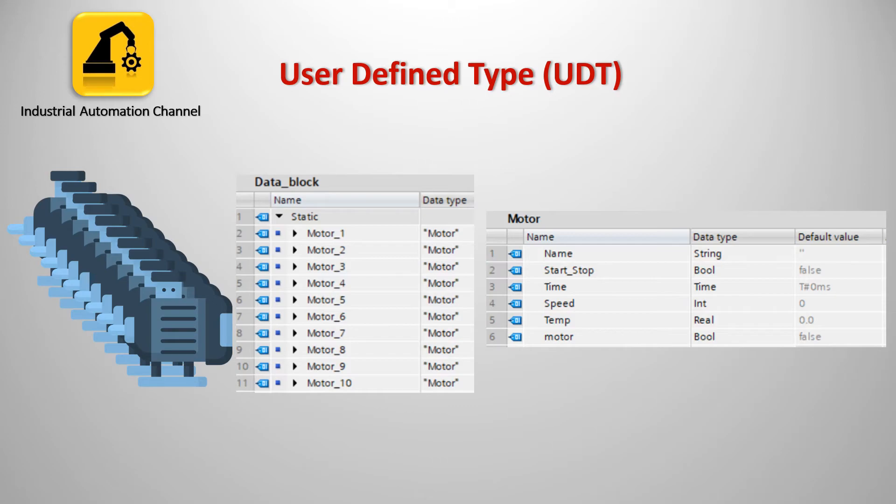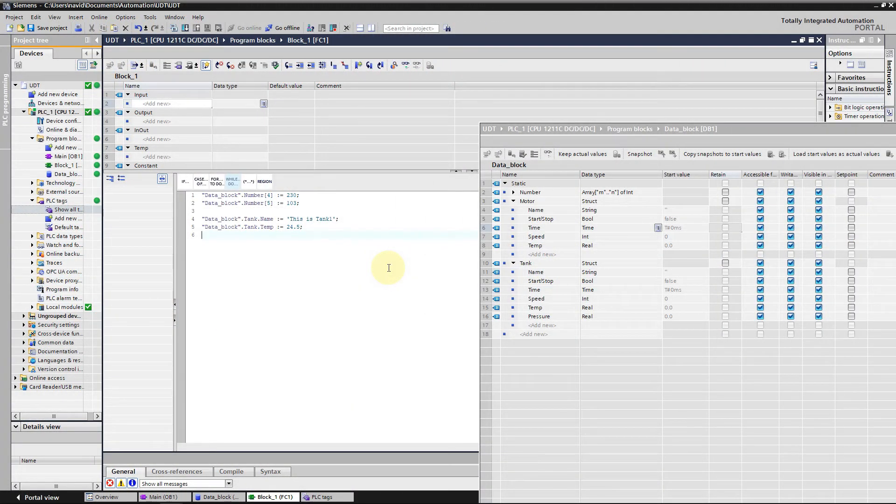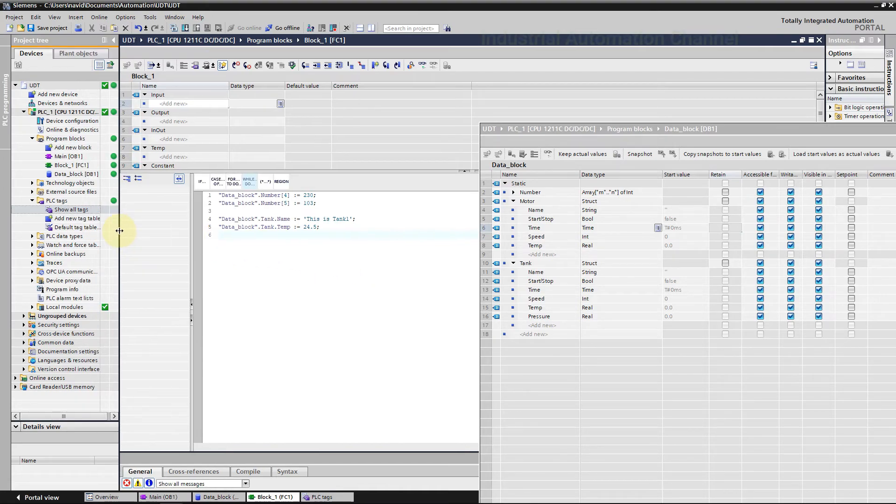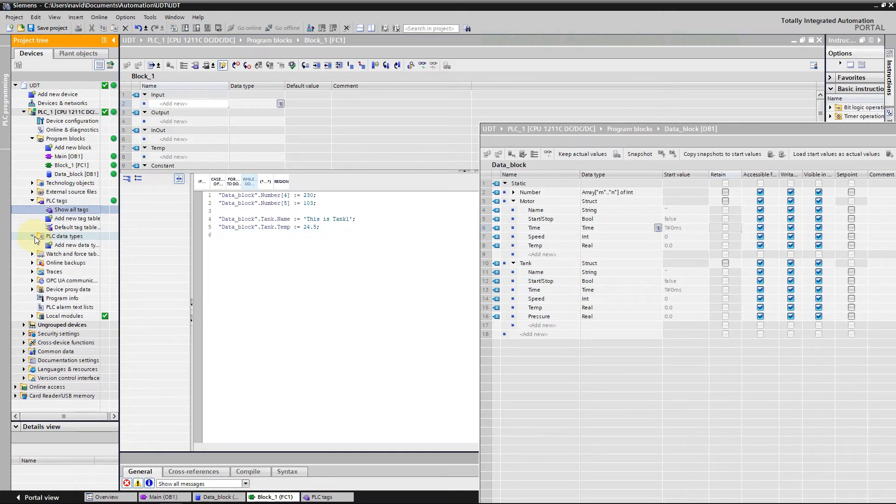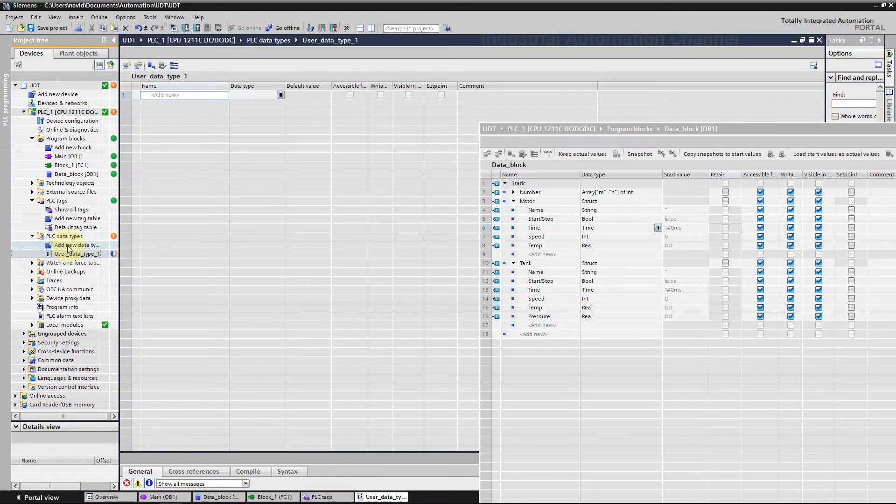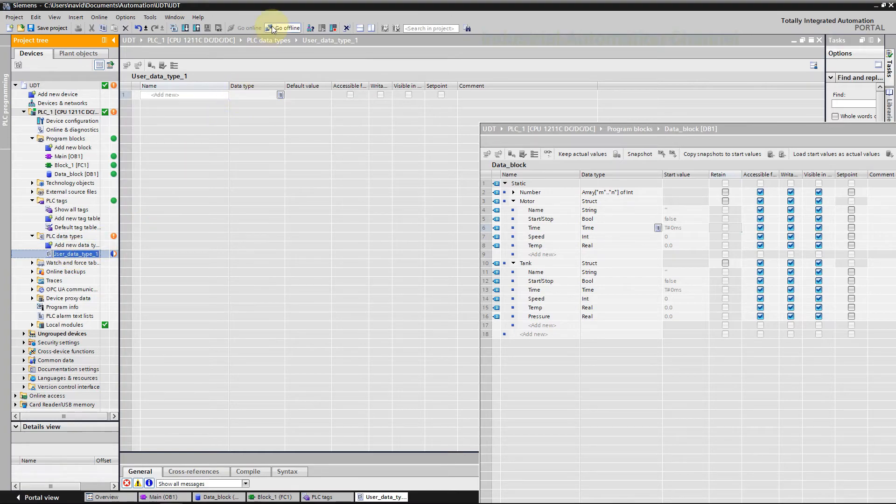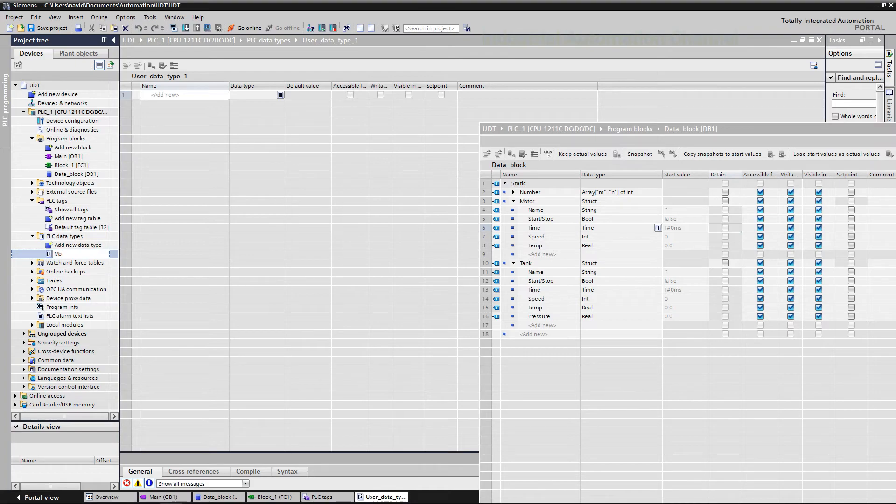When generating data blocks you can designate PLC data types as a type. You can create several data blocks based on this type, all of which have the same data structure. These data blocks can be customized by changing the actual values for the appropriate task. Let us now continue by creating a new PLC data type. In the portal under the project tree, navigate to the PLC data type and create a new one. A default name is assigned for the newly created PLC data type. I'm going to change it to motor.